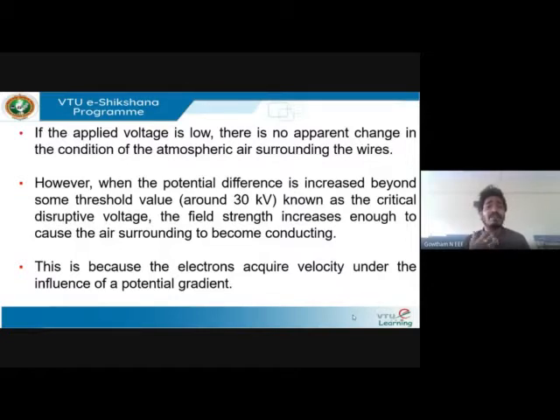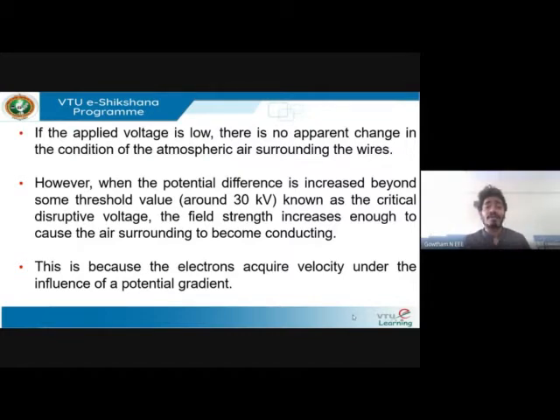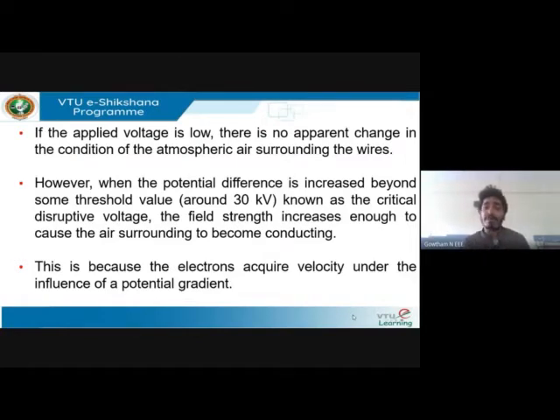If you increase the voltage to about 30 kV — which is called the critical disruptive voltage — the field strength will increase. This field strength causes electrons inside the conductor to ooze out. Since air is the surrounding medium, it gets ionized. The surrounding medium starts becoming conducting, and when electrons flow through the air, air also becomes conducting. That gives you a hissing noise or sparkling — that phenomenon is called corona.